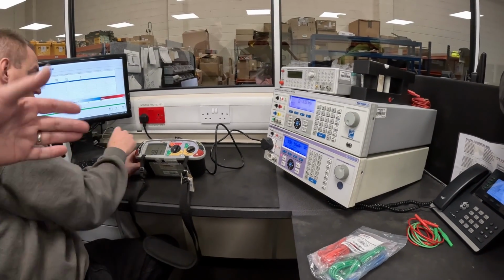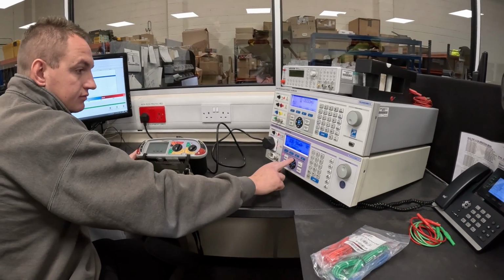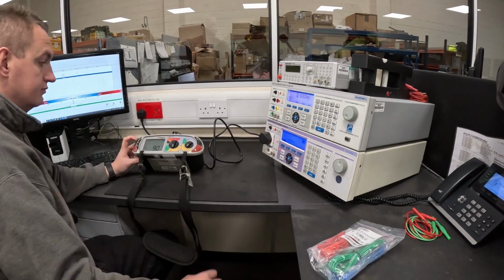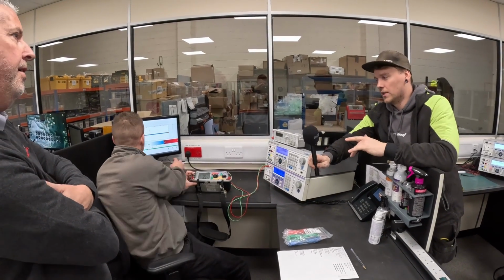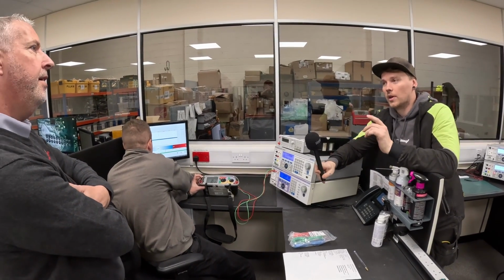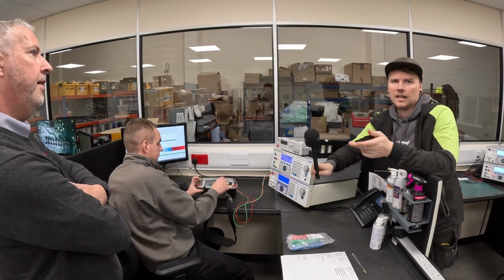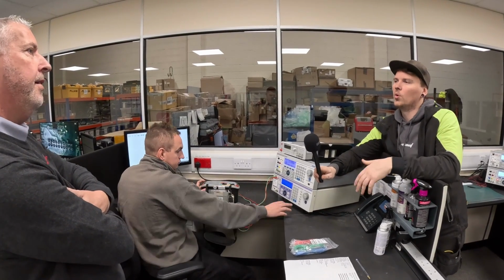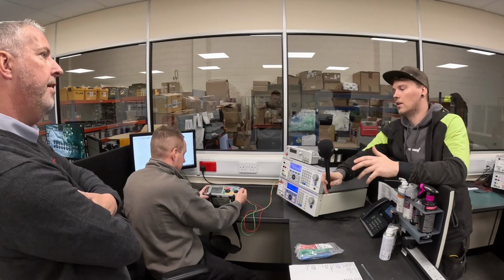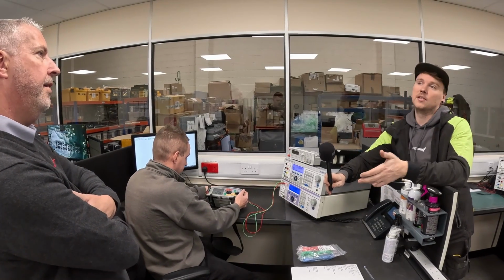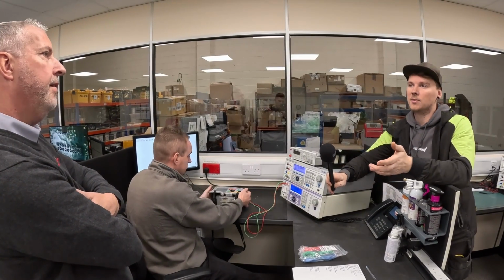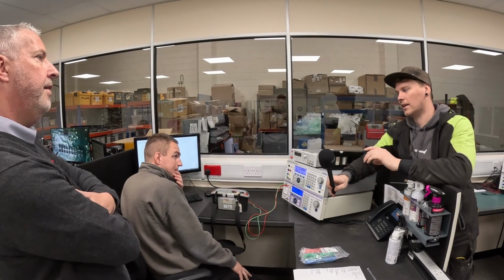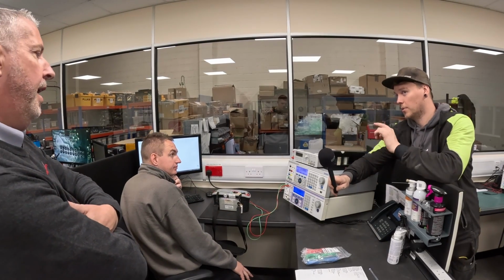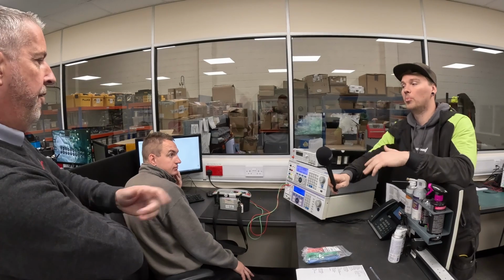Again, the calibrators would trip the bench out if they're on a normal RCD. So I did a video ages ago on insulation resistance on smart switches, where I tried to stick 1,000 volts through a kinetic or similar switch. Everyone always says you can't mega your lighting circuit because you'll break the appliances, but actually that's not the case, because it can detect if something's in line and won't put through 1,000 volts.